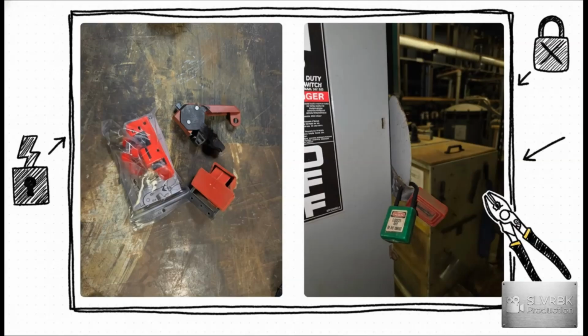To put this into perspective, a true lockout device is a positive restraint. Think about a circuit breaker lockout mechanism, or a heavy-duty danger lock physically securing an electric switch. No one can just casually pull these off. They literally cannot be removed without the specific key, or without using extraordinary, destructive means, like actually coming at the lock with heavy-duty bolt cutters. It provides real, physical security.